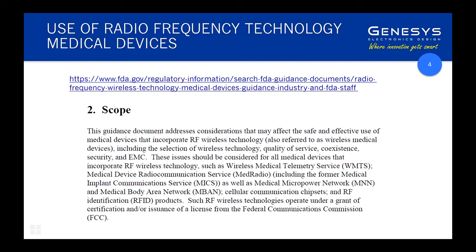A question often arises about the use of radio frequency technology in medical devices — what is allowable? For example, can you have radio transmitters in intensive care wards or operating theatres? This is an area where there are no hard and fast regulatory standards saying what you can and can't do — it's all a case of degree of risk and risk management. The FDA takes a leading role in providing guidance, and I thoroughly recommend having a look at FDA guideline papers where there are no regulatory standards specifically prescribing what you can and can't do.